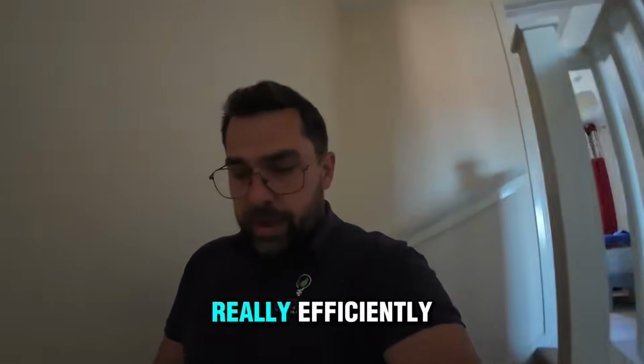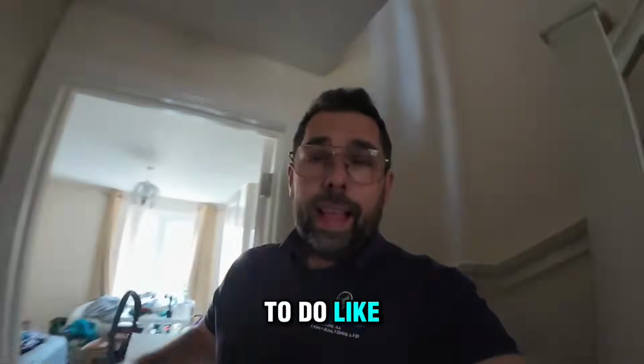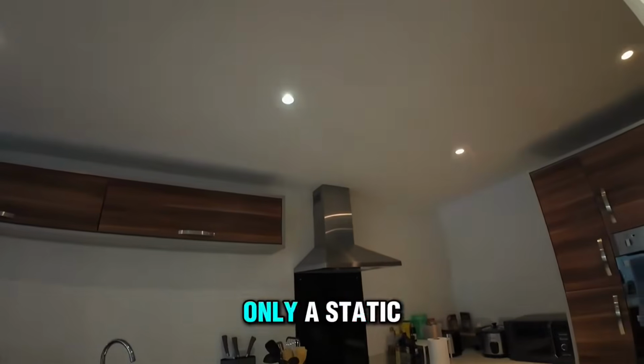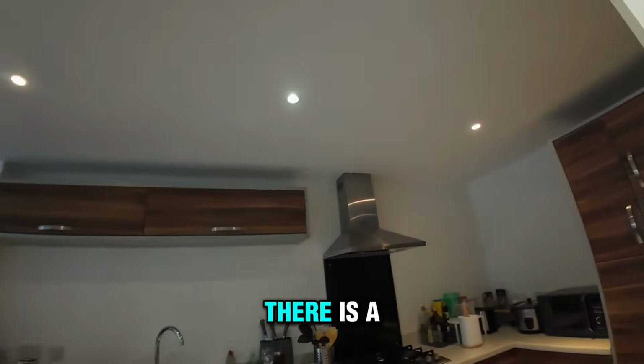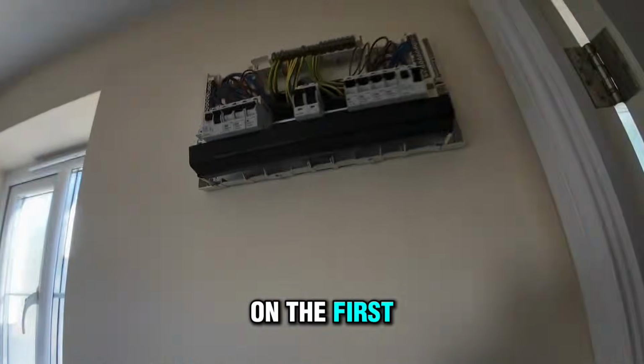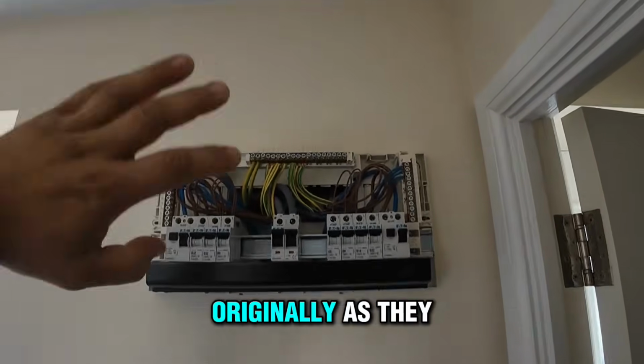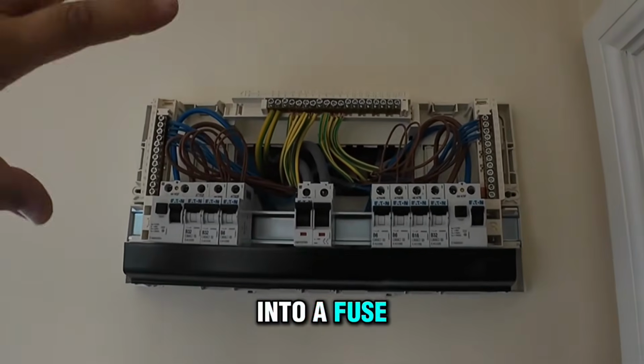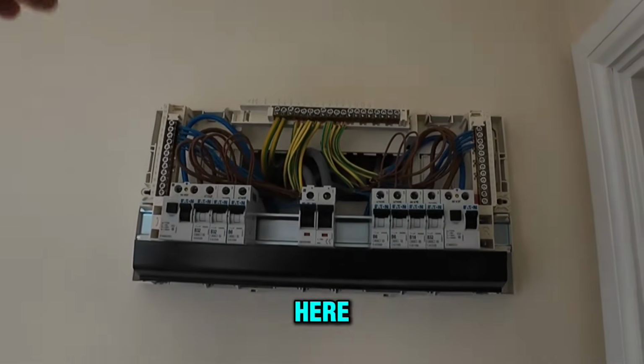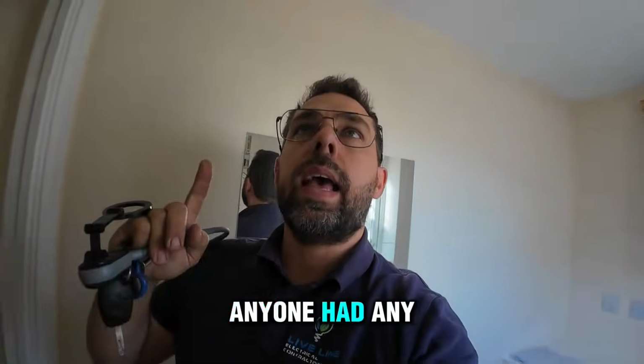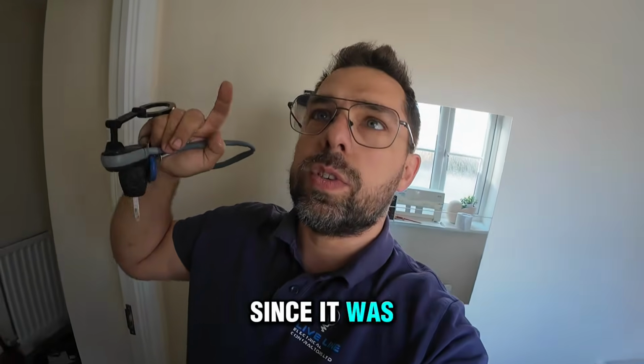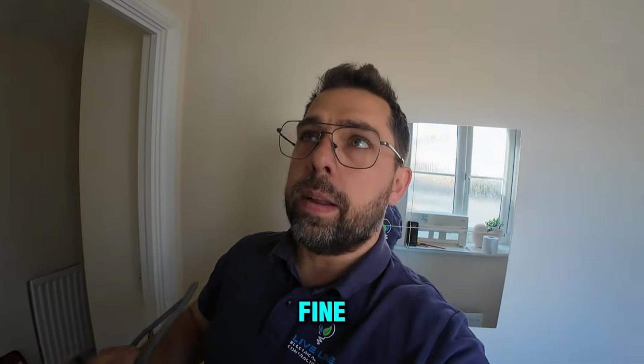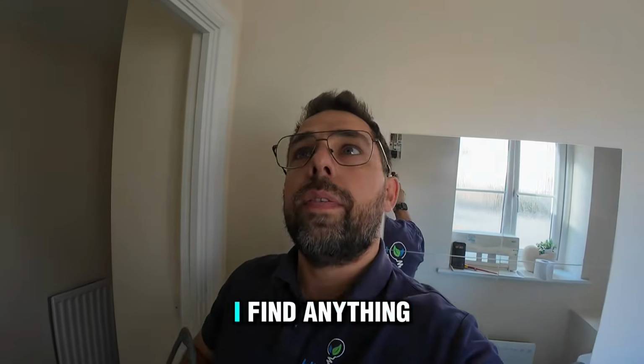So if you, as a client, would like to help us electricians to do our job really efficiently, just help us like this client did at that house. So well done. This is the extractor hood. We'll find out if this is only a static charge that was there or if there is a problem with it. It looks like, at first glance, the cables are originally as they were put into the fuse board. That's how they still are in here. I don't think anyone has had any influence on this installation since it was new, so it should be absolutely fine, but stay tuned to see if I find anything here.